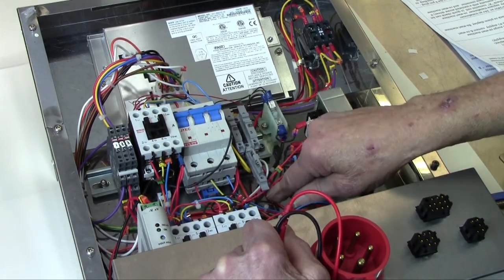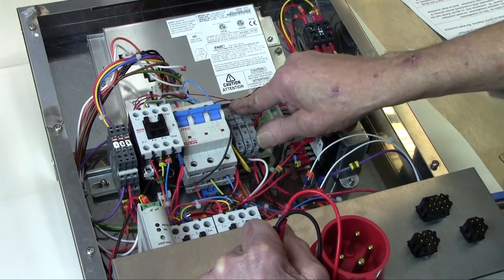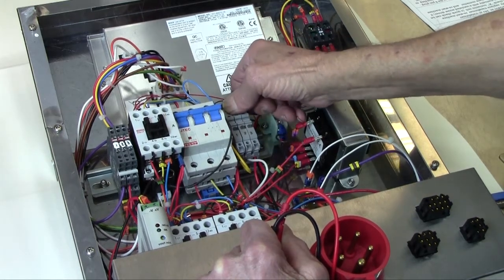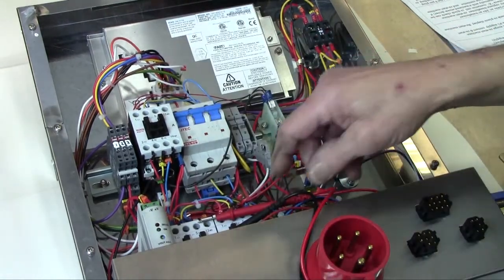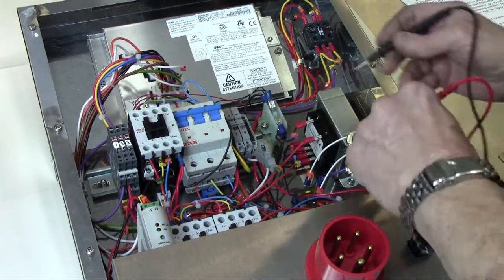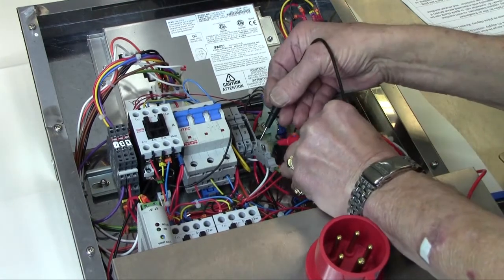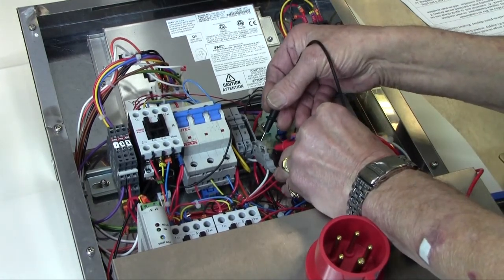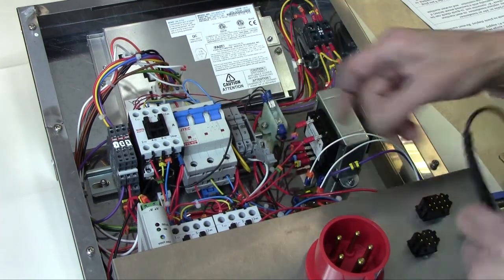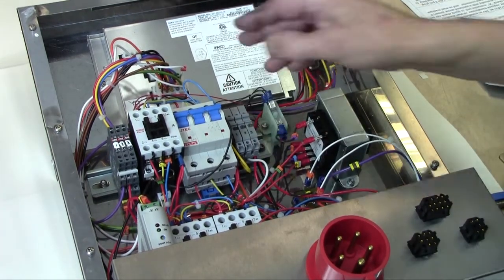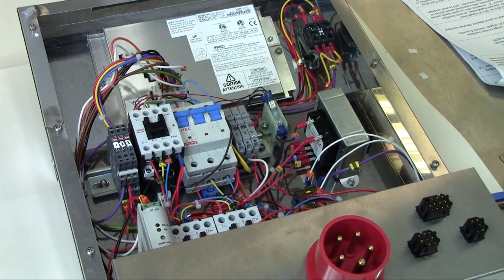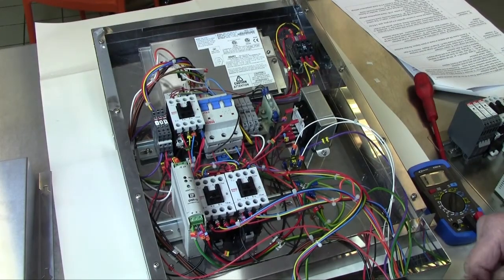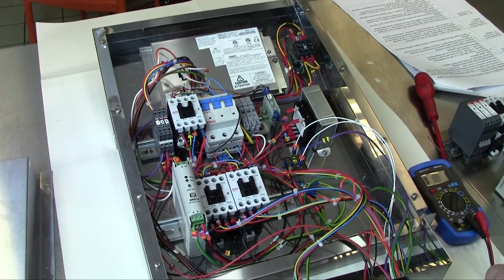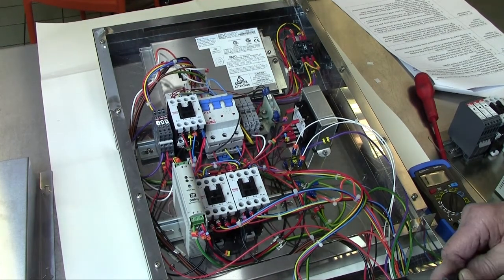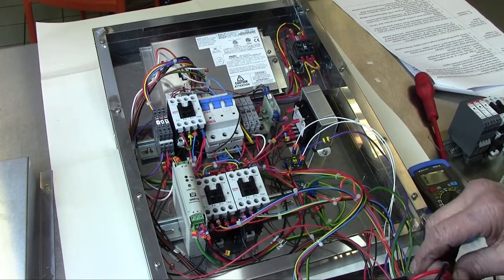If that checks okay, check number 3. Number 3 is a 220 240 volt 1.25 amp fuse that supplies the anti-surge. It's checking okay. If faulty, replace the fuses. After checking fuses and you try to restart the machine and it fails, then check the anti-surge input.